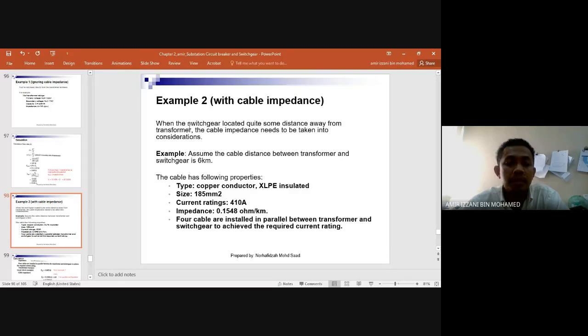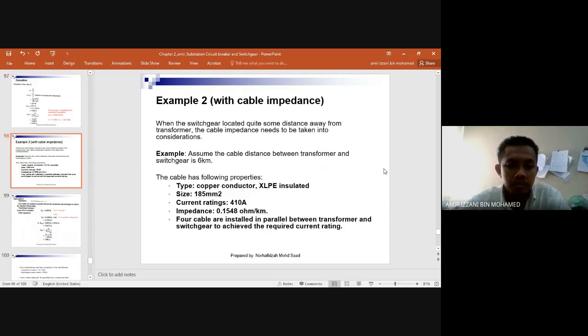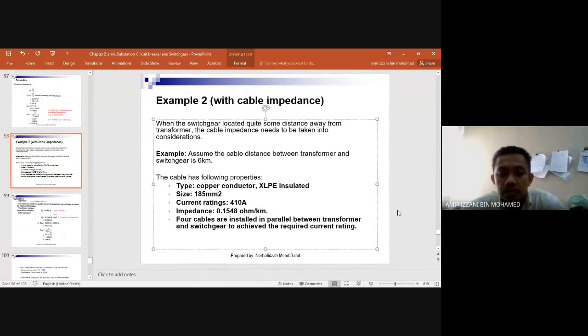With cable impedance. Just now we ignored the cable impedance. Now we consider cable impedance. When the switchgear is located quite a distance from the transformer, we need to take the impedance of the cable into our consideration. For example, here the cable length is 6 km. This is the type of cable and its insulation, and we have the size of the cables, current ratings, impedance per kilometer. 4 cables are installed in parallel between transformers and switchgear to achieve the required current rating.